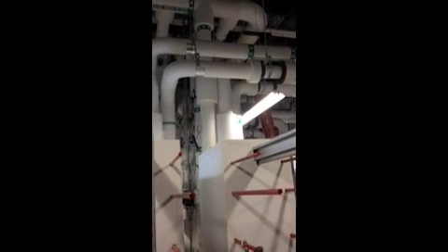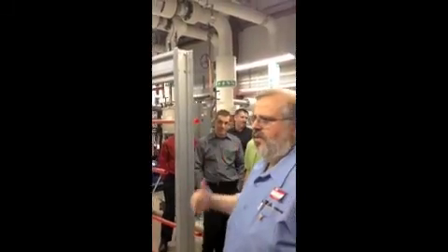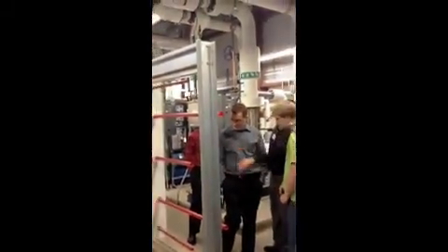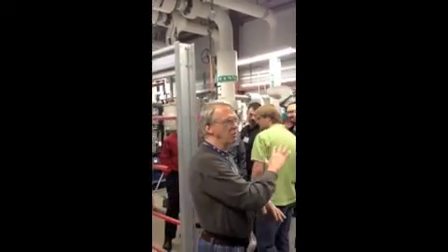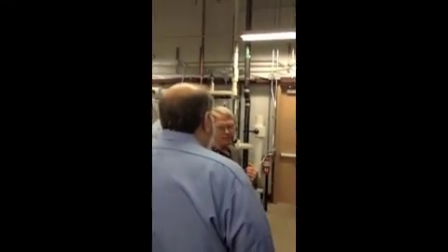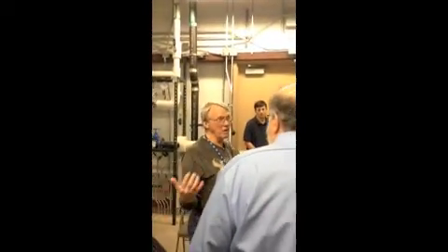Questions? You don't have any freezing problems with the evaporator coolers? They actually have heaters in the bottom if it's necessary. But keep in mind that what's going out there through those cooling towers is hot water. The problem would be if they're not used during the winter, if you're using only one of them and the other three are sitting idle, then they can freeze. Okay, we'll move on this way to the north.